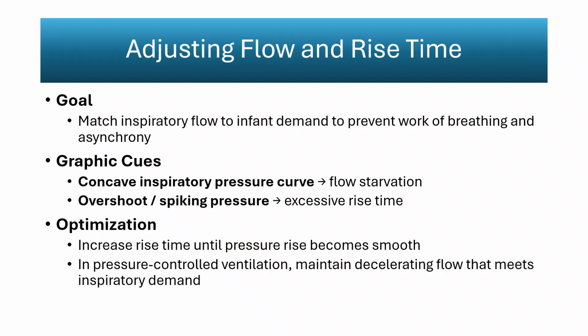Optimization focuses on shaping a smooth and physiologic pressure rise. Increasing rise time gradually corrects the concavity and ensures the ventilator is matching the infant's instantaneous flow needs. In pressure-controlled ventilation, the goal is a decelerating flow pattern that remains adequate throughout inspiration without producing excessive initial flow. Adjustments should be made in small increments while observing several consecutive breaths to confirm a stable response. Proper tuning of flow and rise time improves synchrony, reduces respiratory workload, and prevents misinterpretation of pressure abnormalities caused by flow mismatch rather than true compliance or resistance changes.